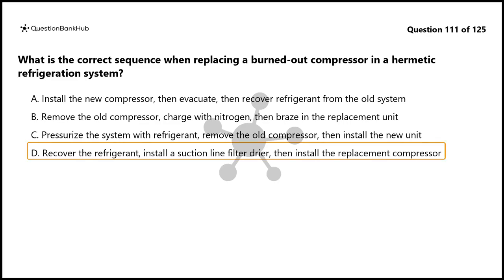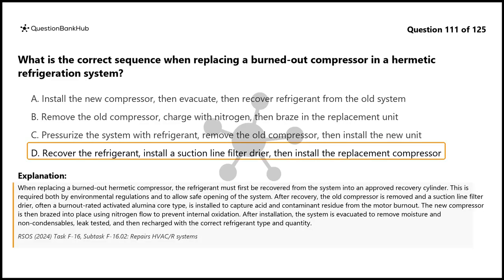The correct answer is D. When replacing a burned-out hermetic compressor, the refrigerant must first be recovered from the system into an approved recovery cylinder. This is required both by environmental regulations and to allow safe opening of the system. After recovery, the old compressor is removed and a suction line filter dryer, often a burnout-rated activated alumina core type, is installed to capture acid and contaminant residue from the motor burnout. The new compressor is then brazed into place using nitrogen flow to prevent internal oxidation. After installation, the system is evacuated to remove moisture and non-condensables, leak tested, and then recharged with the correct refrigerant type and quantity.